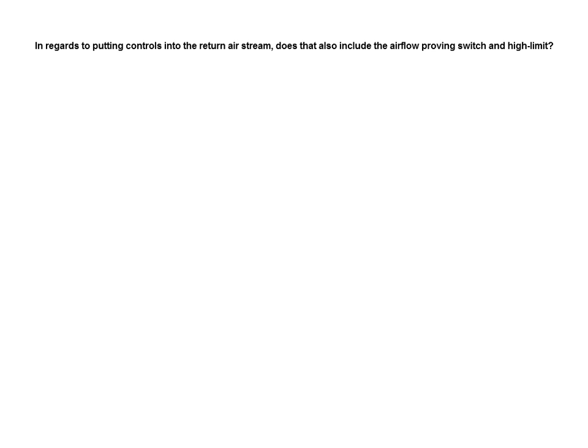Question: When putting controls in the return air stream, does that include the airflow-proving switch and high limit? No — the airflow switch should be just before your steam dispersion grid to confirm airflow is passing over it. The high limit should be, as a rule of thumb, about three times your absorption distance downstream. So if you have a two-foot absorption distance, place it six feet from the steam dispersion grid. The high limit ensures that right after steam is introduced, you don't condense on duct walls — it keeps RH below 80–85%. It's only the room control or main control that goes in the return air stream.